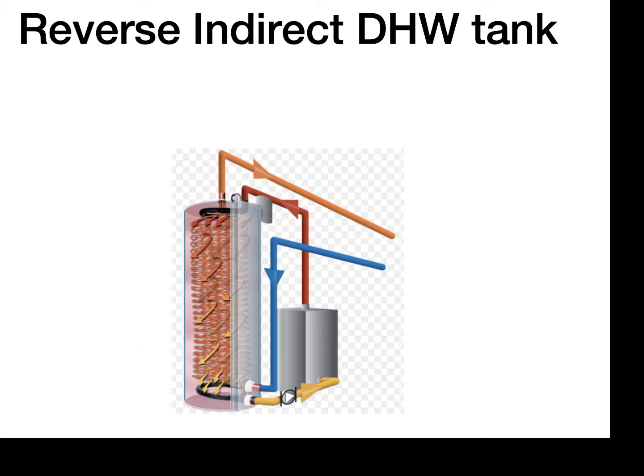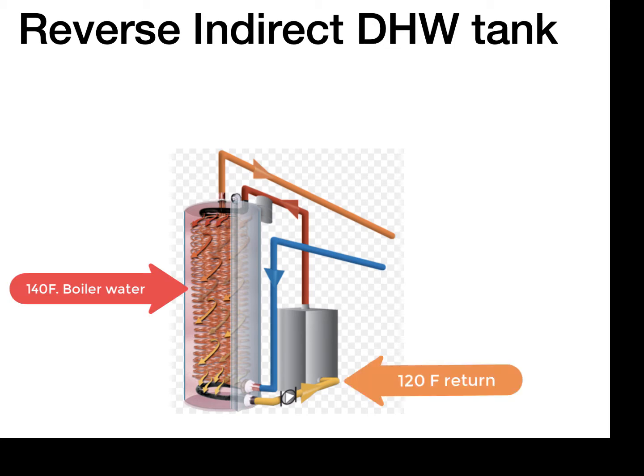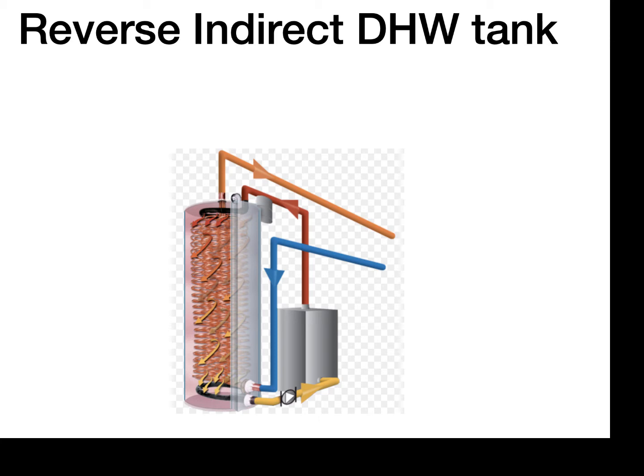The key advantage of this type of system is that with the large surface area, it only requires an approach water temperature from the heat source, typically only 10 degrees hotter than your desired water tank temperature. So if you need 130 degree Fahrenheit water, then essentially you have to hit it with 140 degree Fahrenheit boiler water, which will result in a return water temperature back to the heat source that will and can cause condensing. This is fine if you have a condensing appliance. If you do not have a condensing appliance, you have to be careful that you do not create any long-term condensation production issues that will become a problem with the maintenance and operation of the heat source itself.